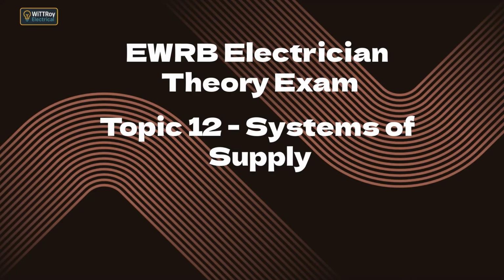12.2b. Explain reasons for earthing neutral conductors at multiple points in the LV distribution system. Earthing the neutral at multiple points stabilizes the neutral voltage, reduces touch voltages, ensures high fault current for rapid disconnection, and increases safety across the entire network. Without multiple earthing, the system would be less stable and fault clearance less reliable.